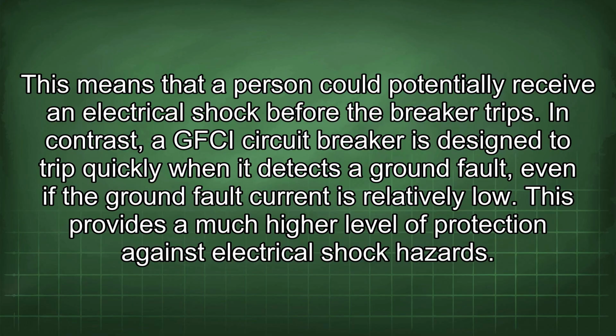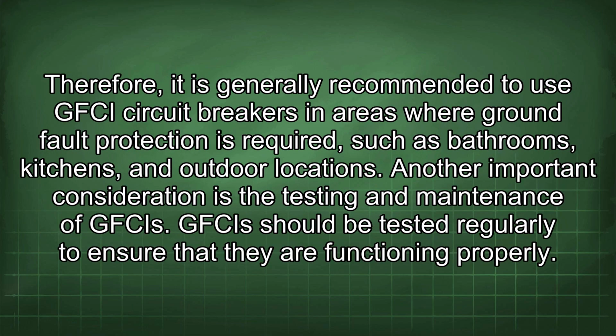In contrast, a GFCI circuit breaker is designed to trip quickly when it detects a ground fault, even if the ground fault current is relatively low. This provides a much higher level of protection against electrical shock hazards. Therefore, it is generally recommended to use GFCI circuit breakers in areas where ground fault protection is required, such as bathrooms, kitchens, and outdoor locations.